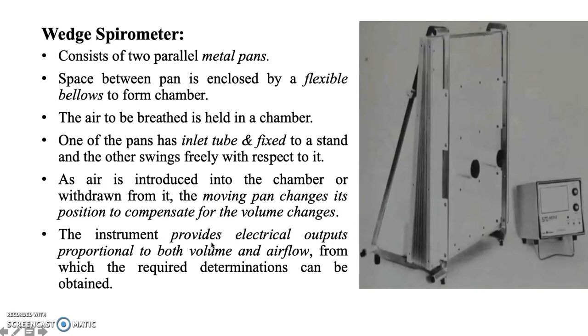Out of these two pans, one pan will be fixed to a stand, so it will not move, and it will also have an inlet tube, whereas the other pan will swing freely. If the patient inhales or exhales, air may be introduced into the chamber, or it may be withdrawn from it. The chamber will then expand and compress, which leads to a change in the position of the moving pan. Hence, this instrument provides an electrical output which is proportional to the volume of the lungs and the airflow.